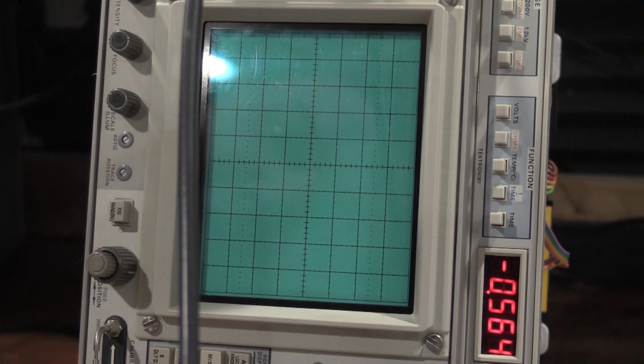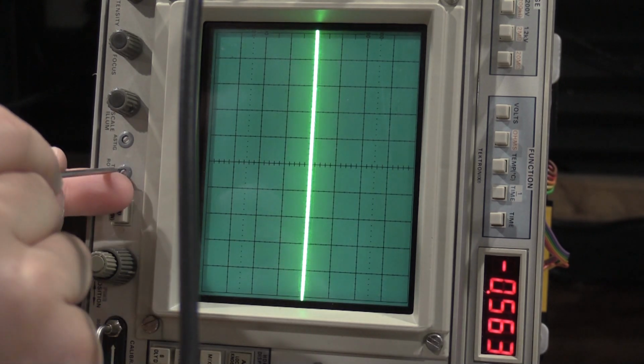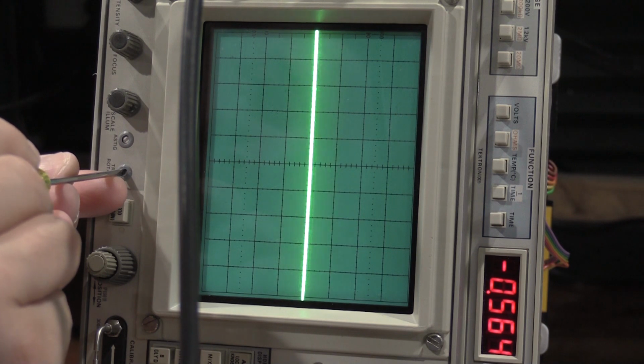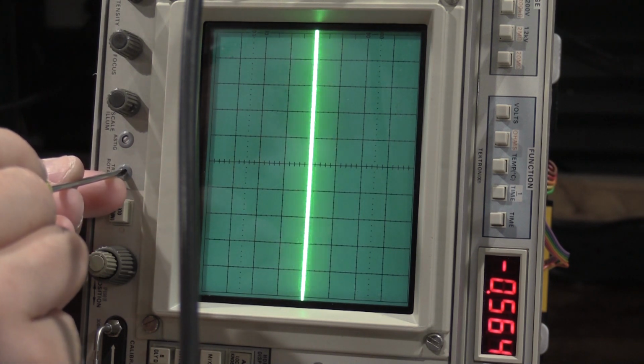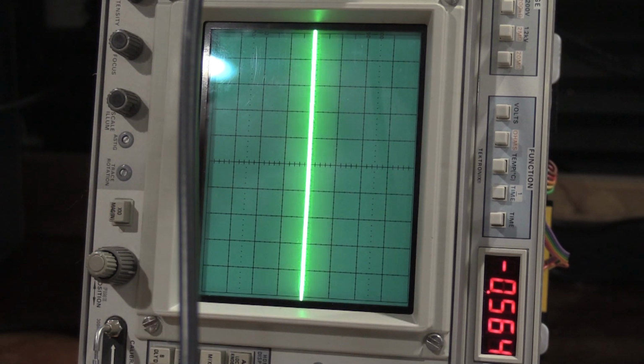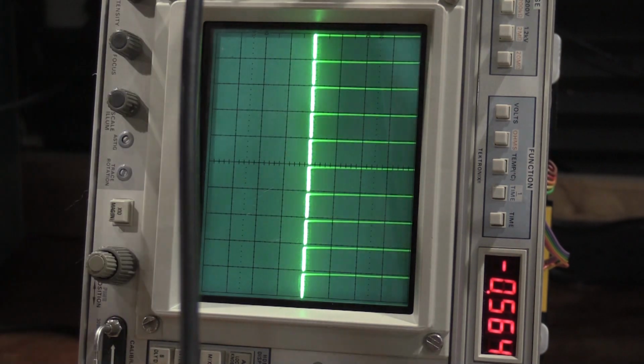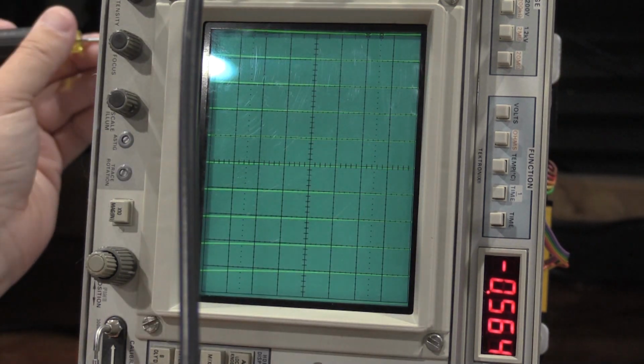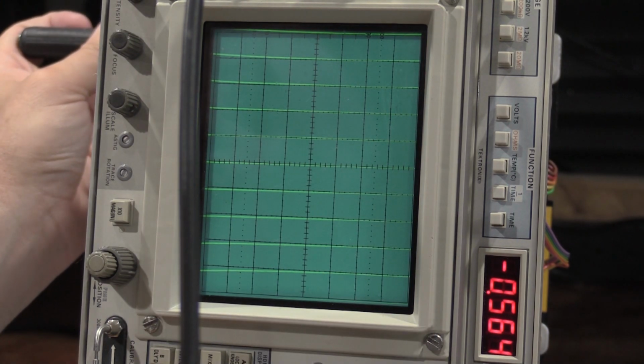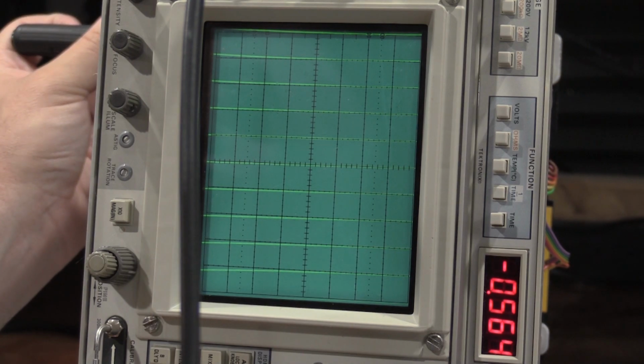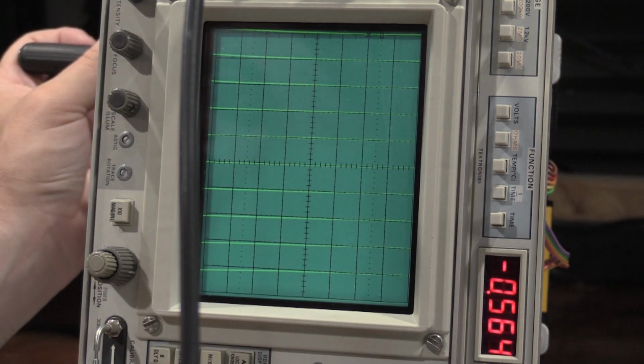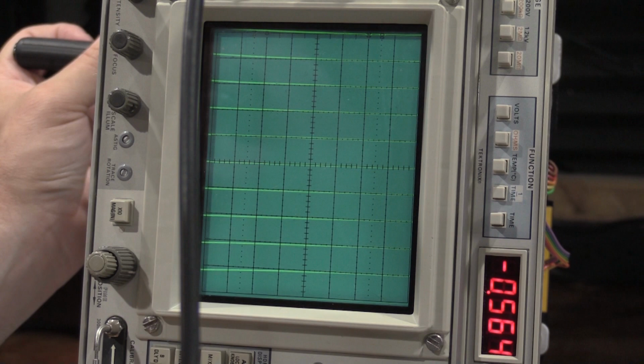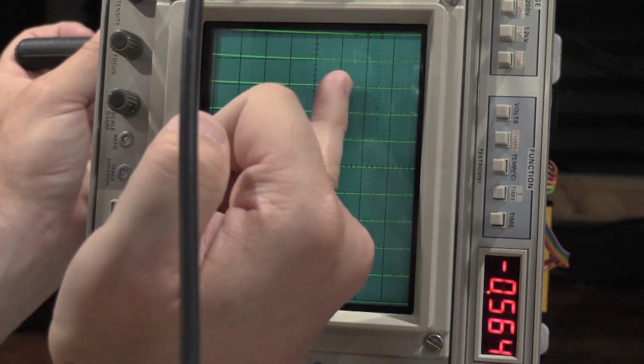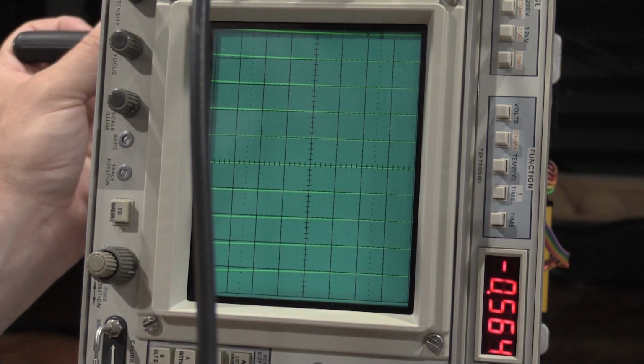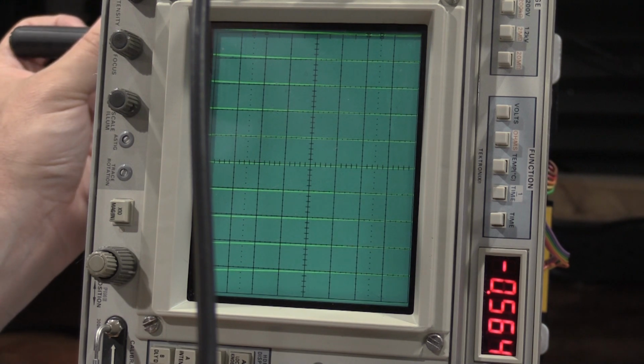Now, trace rotation. This was actually pretty far out. I don't know if this was just drift or if somebody has been in here before me. But of a lot of the scopes that I've worked on, this one's probably been the worst for the tube in terms of adjustment. Oh, now that's getting dialed in real good. Only pay attention to the top half. The bottom half, this is where the curve kind of comes down from the time mark.